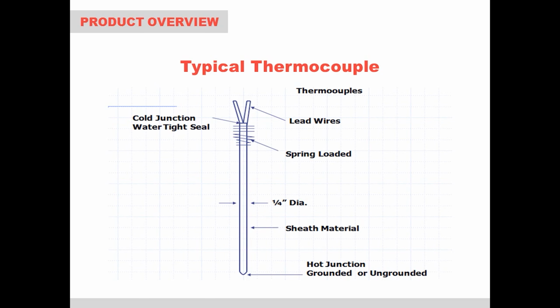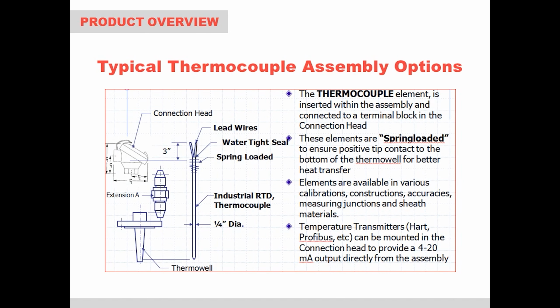A typical thermocouple looks like this. Starting from the bottom, you have the hot or measurement junction with a welded cap on the end. Lead wires are soldered on the back, and a moisture-resistant potting compound helps seal the back connection from moisture. A spring is added for use in a thermowell and can be removed if needed. Other options include the addition of a thermowell, a protective tube, that is inserted into the process so that the thermocouple can be easily replaced without shutting down the line or process to remove the sensor. Various extension options are available to get the connection head up and away from heat sources so that the terminations can be made in an ambient temperature zone that is safe and convenient. Finally, an optional head-mounted temperature transmitter can be utilized to provide a 4 to 20 milliamp signal rather than running long distances with extension wires to a controller. These are just some of the packaging options available with a typical spring-loaded thermocouple.